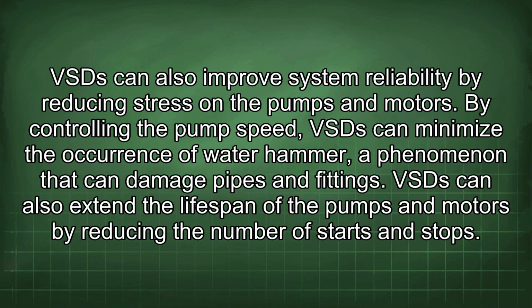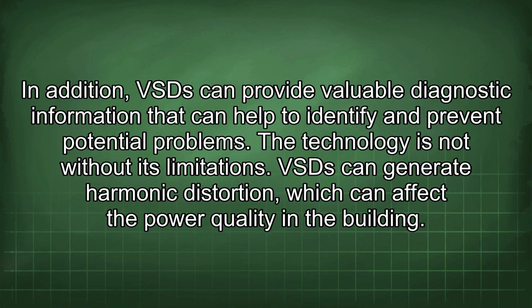VSD can also improve system reliability by reducing stress on the pumps and motors. By controlling the pump speed, VSD can minimize the occurrence of water hammer, a phenomenon that can damage pipes and fittings. VSD can also extend the lifespan of the pumps and motors by reducing the number of starts and stops. In addition, VSD can provide valuable diagnostic information that can help to identify and prevent potential problems.